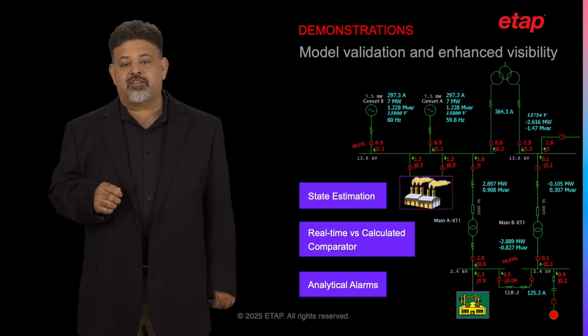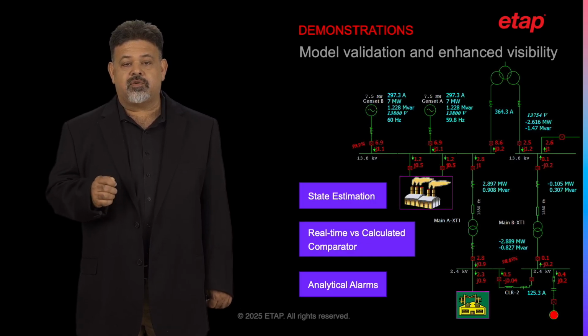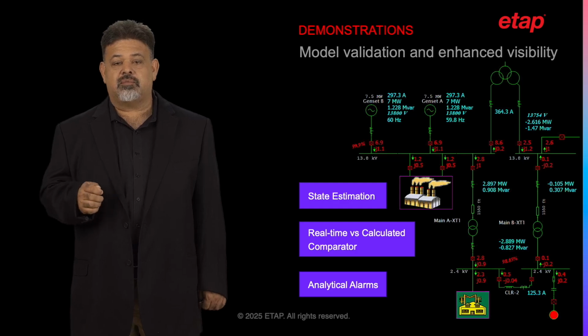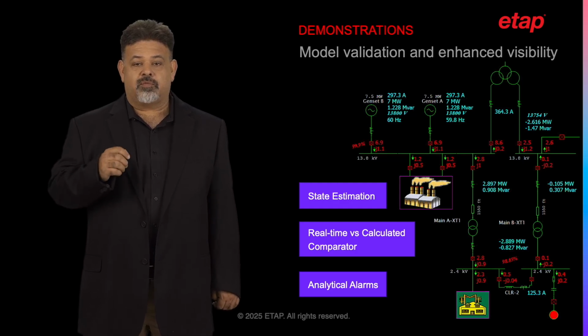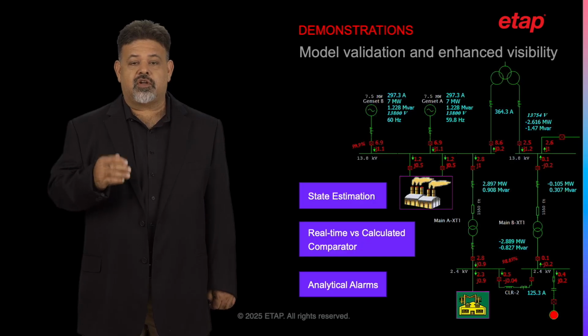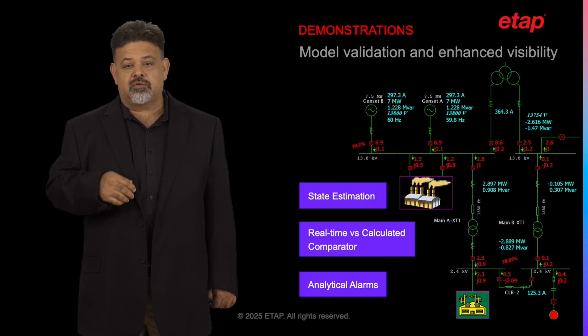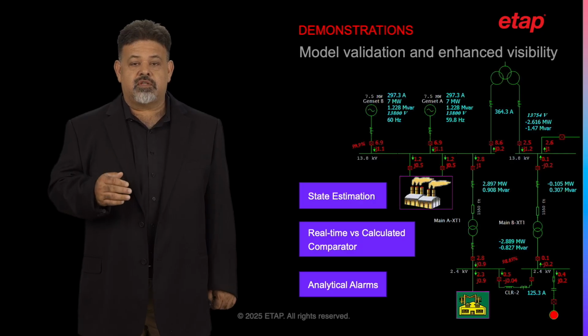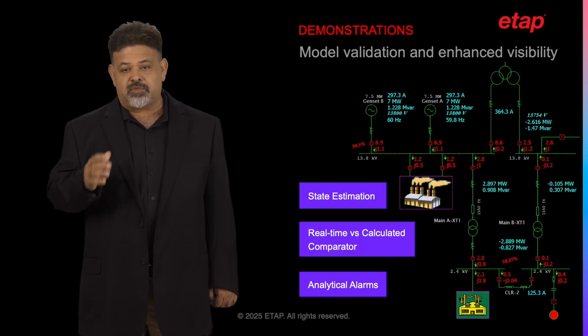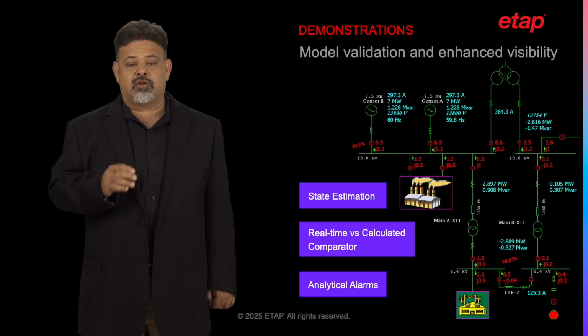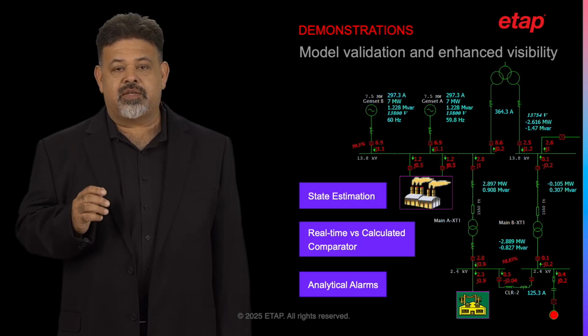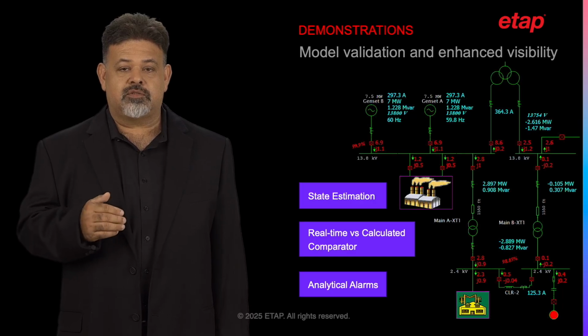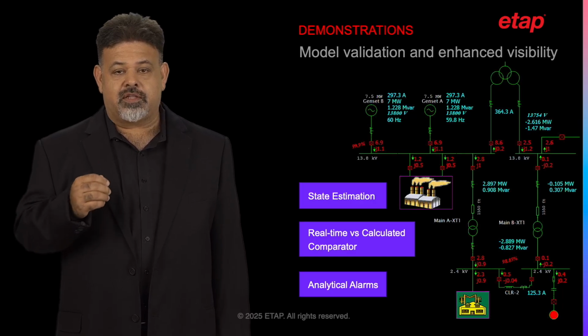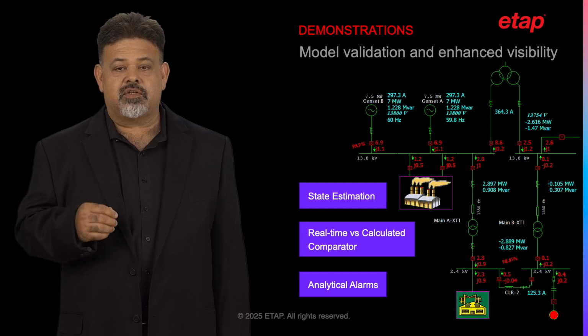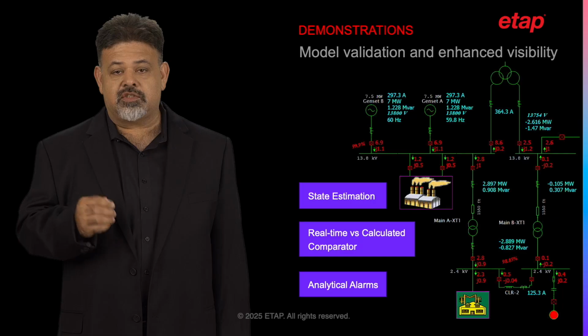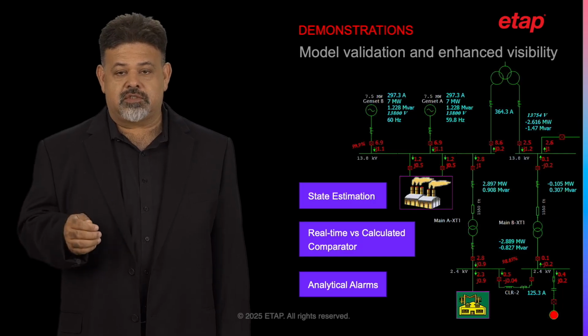The state estimation enhances visibility features, displays additional power flow measurements in areas where no instrumentation is available. This is particularly useful as for many electrical operations, it may not be feasible or cost-effective to add power monitoring instrumentation to all their assets. Leveraging the digital twin and available power monitoring data, the state estimation feature can make visible the power flow across the model. State estimation alarms notify engineers and operators of potential risk with the operation. By understanding the digital twin model and the live measurements, the state estimation feature is capable of notifying operators of alarm conditions due to overload or operating bus voltage.